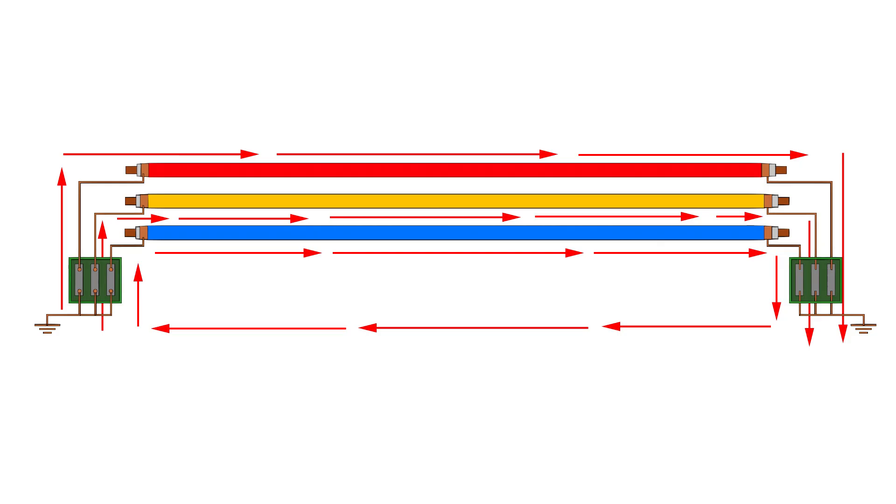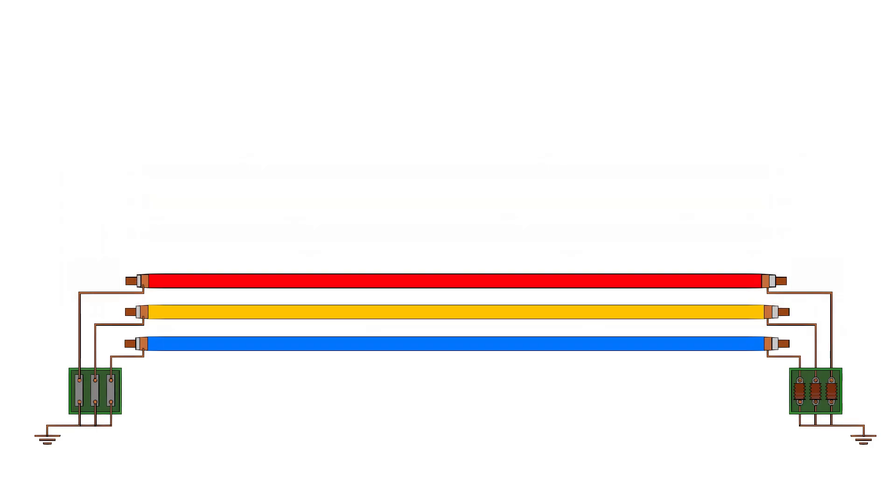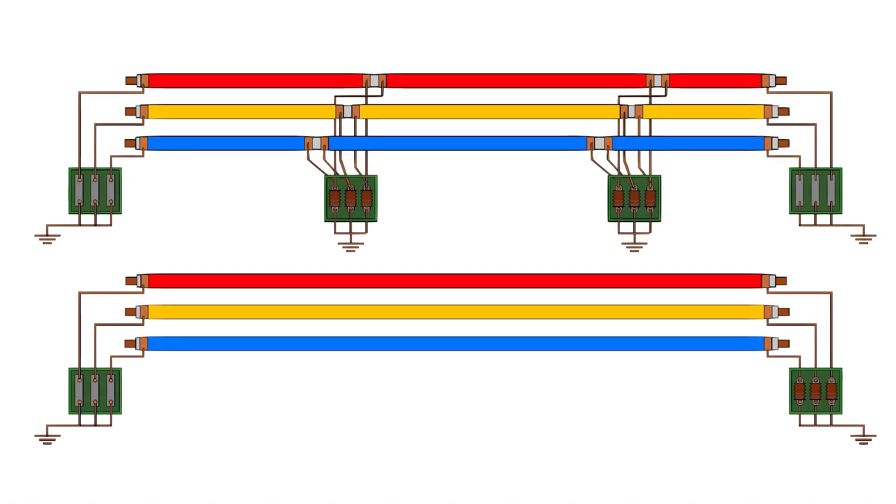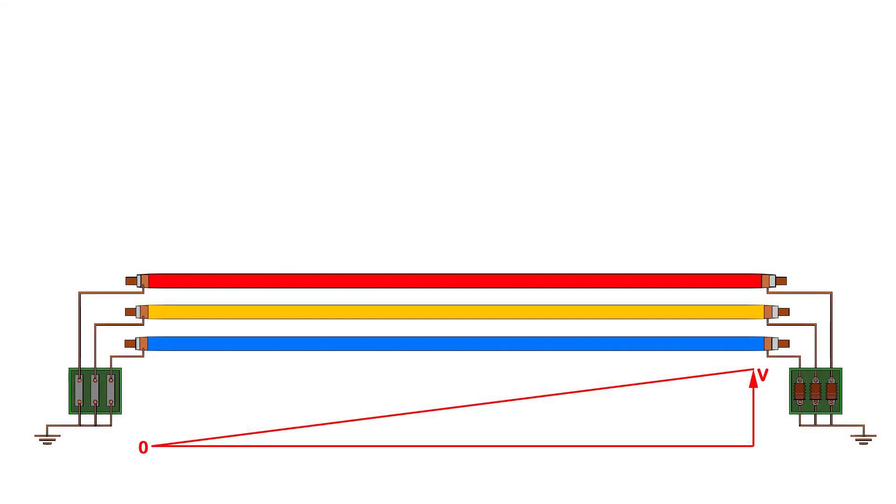To avoid this, engineers often use single-end or cross-end bonding. But single-end bonding leaves one end floating, which can allow dangerously high-induced voltage, especially as you move further from the earthed side. This is actually open at this end.